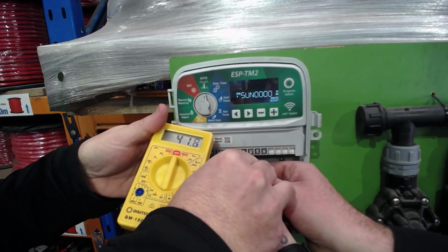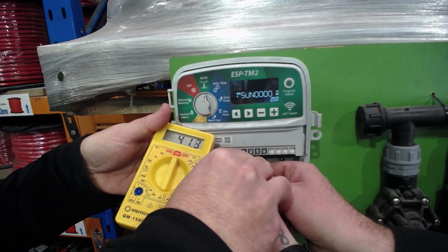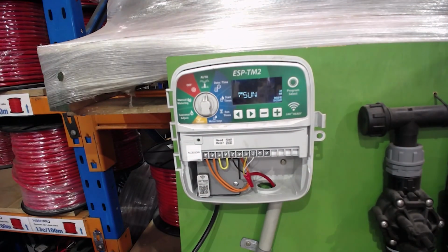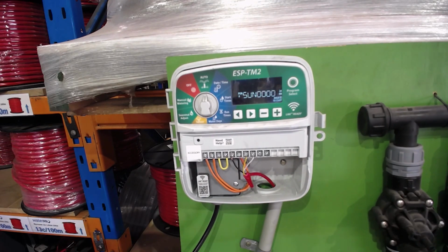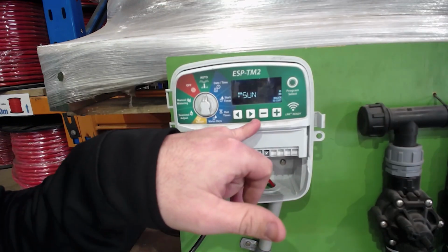Can you guys see that number on the screen? Yep, so Rainbird coils will tend to give me around that 41 ohms of resistance. You'll see a little bit more resistance than that because you've obviously got cable going out to it. There's literally only this amount of cable. But that tells me that I've got a good coil on that valve.